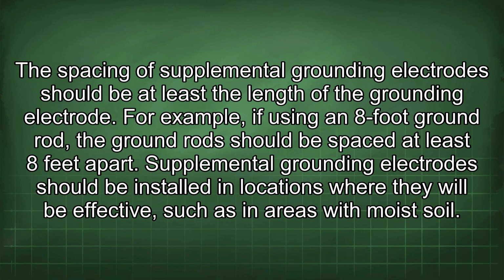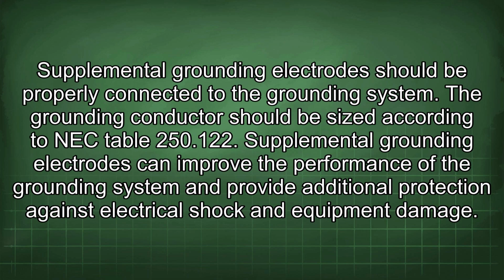Supplemental grounding electrodes should be installed in locations where they will be effective, such as in areas with moist soil. Supplemental grounding electrodes should be properly connected to the grounding system. The grounding conductor should be sized according to NEC Table 250.122. Supplemental grounding electrodes can improve the performance of the grounding system and provide additional protection against electrical shock and equipment damage.